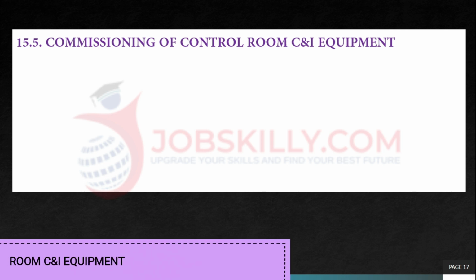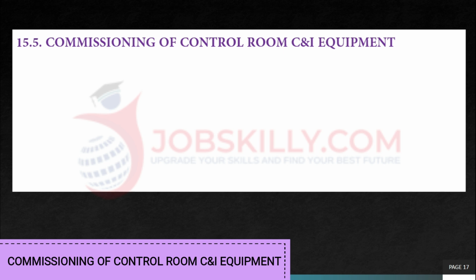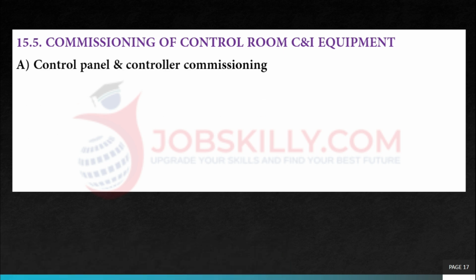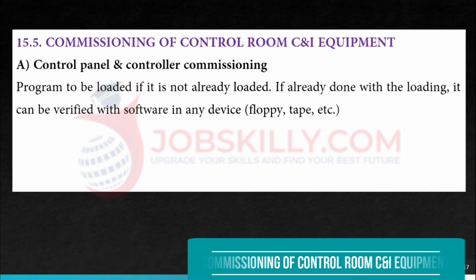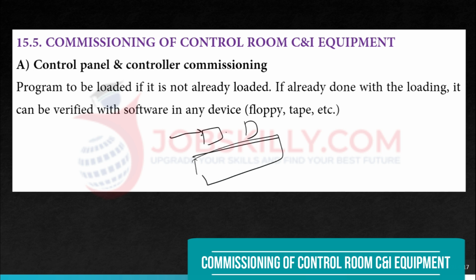Commissioning of control room C&I equipment. Now, whatever instruments are present in the control room, we will see in this part of the chapter. Control room panel and controller commissioning. What is that? The program is to be loaded if it is not loaded. We bring the DCS from the OEM and we set it up at the control room. Sometimes the program will be loaded before it comes here. Sometimes we have to upload the program at the site. If the loading is already done, it can be verified with software in any device.